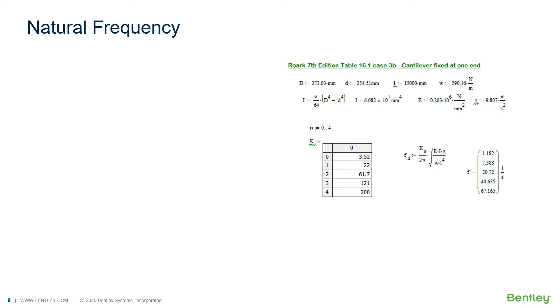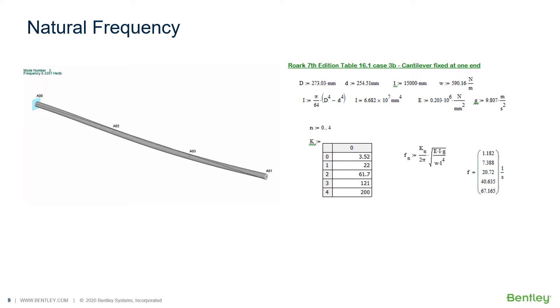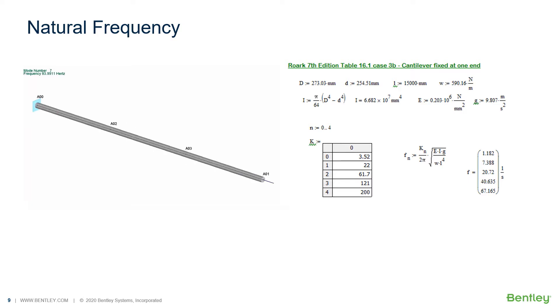Here we have refined the model by manually adding in mass points. We now see the first mode is nearer to what was calculated. We also see that we have a second and a third mode before the axial mode that was the second one in the first exercise. These still don't coincide with the exact calculated values, however, but we seem to be getting closer.